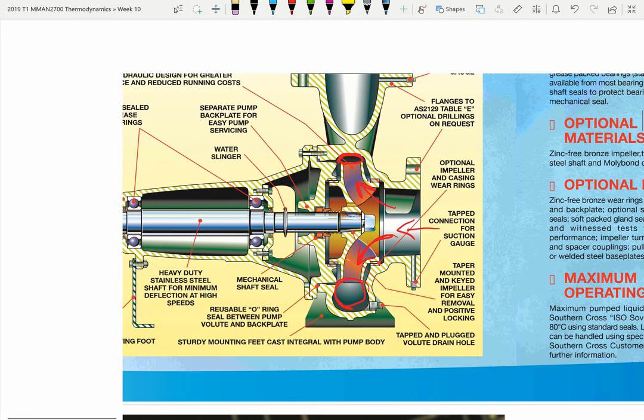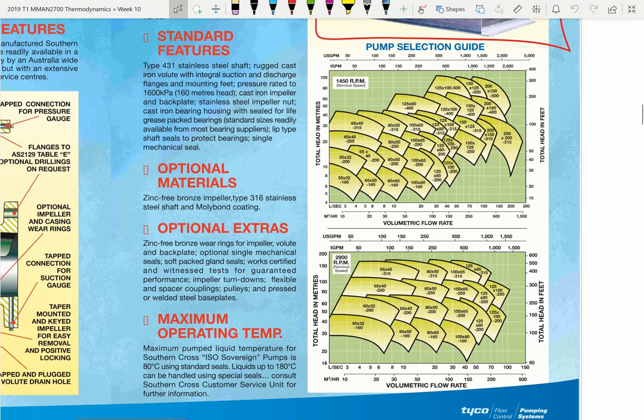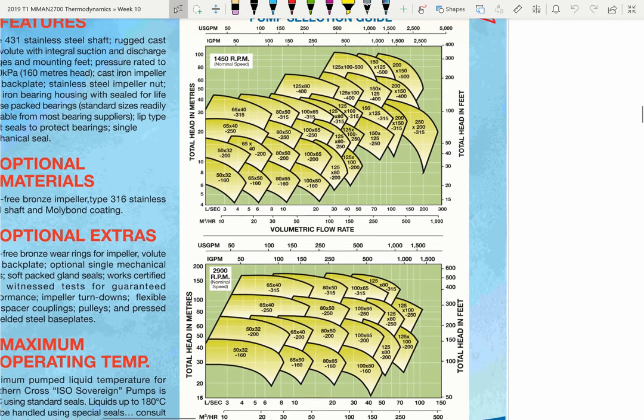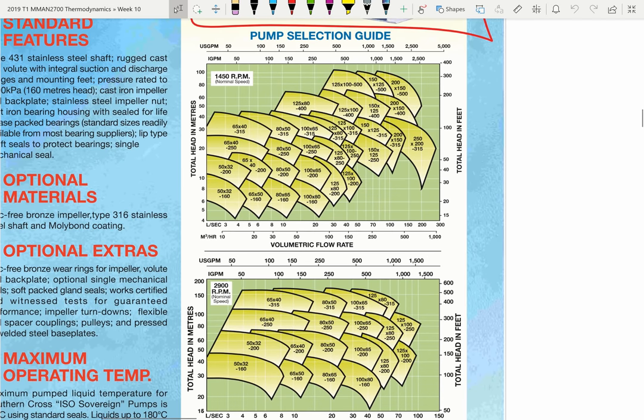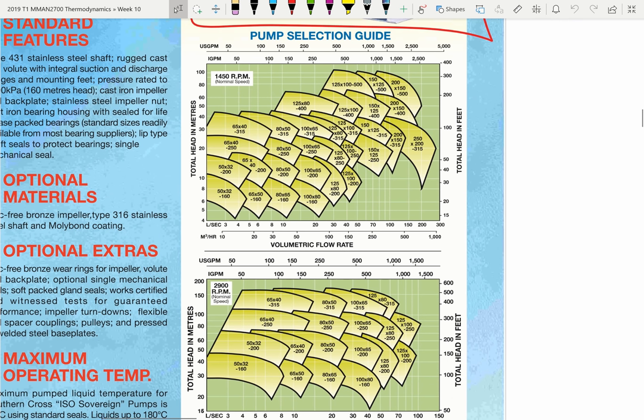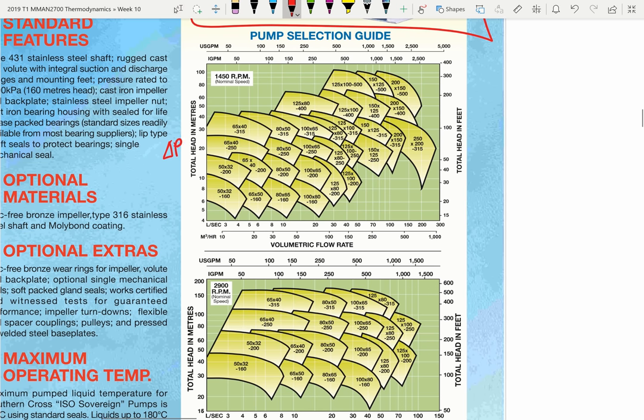That shows you some components and gives you a sense of what's going on. Let's come over to these curves showing some important information. This is the pump selection guide. Now we know about pump curves, so I want you to be thinking in terms of pump curves when you look at these pumps. The numbers in the middle are the designations of the pumps: 50 by 32 by 160, or 65 by 50 by 160. Total head in metres is on the vertical axis — think about this in terms of ΔP — and volumetric flow rate is along the bottom. The bottom axis is logarithmic — actually it's log-log — which lets us span a large range of values on a small graph.